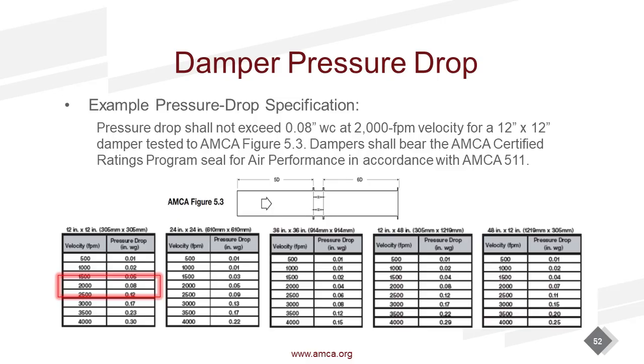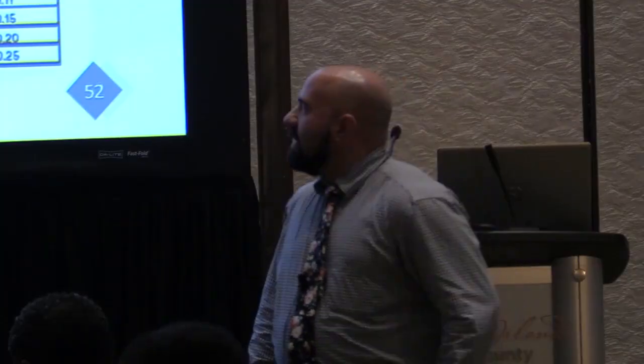How many of you design engineers actually schedule your dampers? Wow, you all just broke my heart. Did you hear that? That was the sound of my heart breaking. Dampers should be scheduled. I know, why? Putting a little line on a drawing and expecting everybody to understand what that damper is, what the service clearance is, what the conflicts are, is doing nobody any favors. You know why dampers create such a problem? Because we don't think about them enough in our design, in our planning. They're an afterthought. Oops, that was a rated wall. Somebody write an RFI and slap a damper in it. I wish we had a little more forethought, a little more planning.